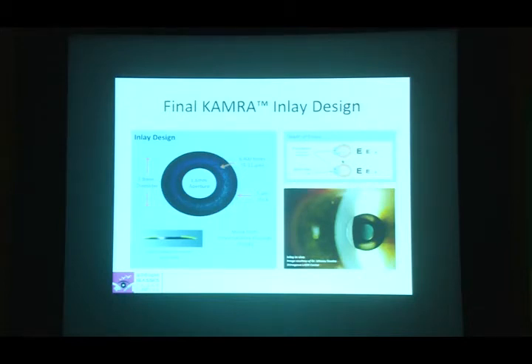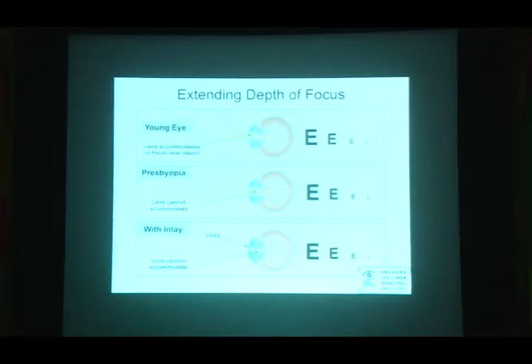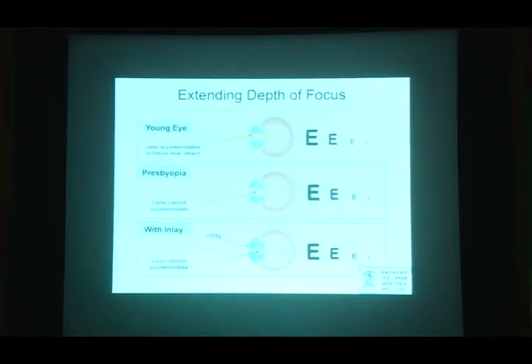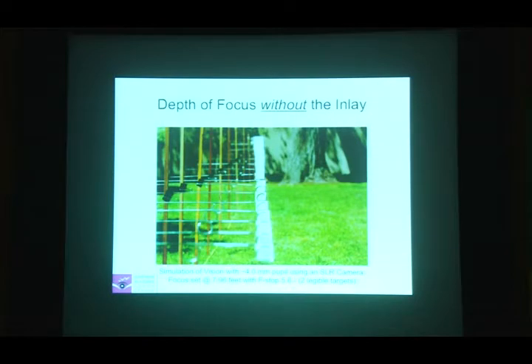This was simulated by Dr. Jack Holladay in his backyard. Using an SLR camera set at 4 mm pupil, f-stop 5.6, focus at 7.96 feet, you see only 3 of 15 targets clearly. When the setting is changed to simulate a 1.6 mm pupil — f-stop 22 — the entire range of vision becomes clear. This explains why a 1.6 mm aperture was selected for the Kamra inlay.